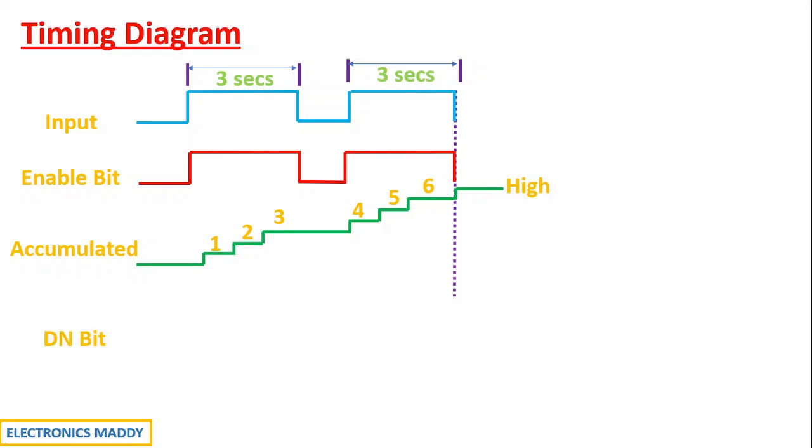How does the done bit vary then? Done bit will be low up to the point where the accumulated value is equal to the preset value. And once it is high, consequently it goes to high state. This was exactly what we saw in the cases. I hope this concept is clear. So the only difference with respect to retentive timer is that it continues to hold the accumulated value even if you turn it off and then turn it on. This is the working of retentive timer.